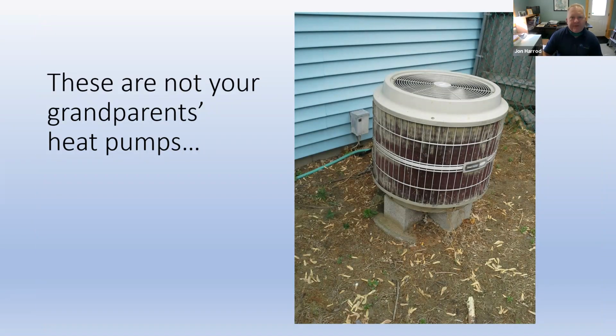One of the things that we have to address when we're talking about heat pumps with customers is some of the negative perceptions they may have had from the older generation of heat pumps, which were never very common in our area, although they're a lot more common in the Mid-Atlantic and the South. People will say, oh, you know, these heat pumps, they're really noisy. They don't work very well below about 40 degrees. We end up relying on our electric strip resistance heat, and so our fuel bills are just exorbitant. And a lot of these things were true of that older generation of heat pumps, and especially when the applications and the control setups weren't done correctly.